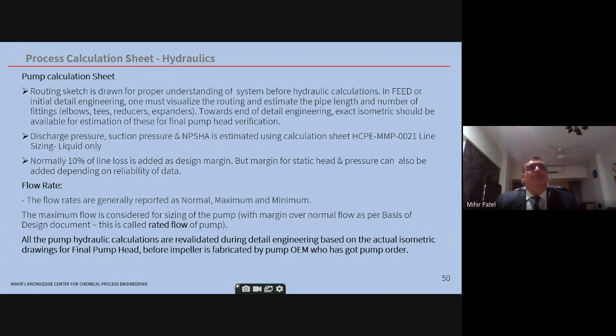A routing sketch is drawn for proper understanding of the system before hydraulic calculations. The plot plan has to be followed, starting from the pump to the end vessel, to see how much distance is there. So in FEED or in initial detail engineering, one has to visualize the routing part. Later on you will have exact isometrics for the final pump head verification. Now discharge pressure, etc., is estimated using, I already have a line sizing template. One can use that. One can also use many empirical formulas for the pressure drop calculations.